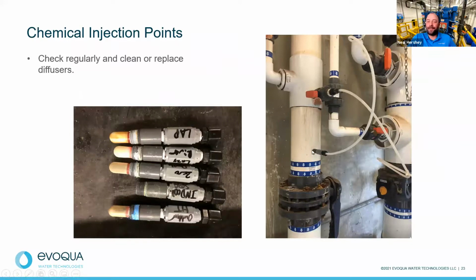In this case here, they're direct tapped into the piping, so to replace this injector you'd have to shut the system down and do that service, which could interrupt your schedule and your program and everything else. It's better to be proactive on these items and make sure you're planning ahead, building it into your routine plan, so it's not a surprise on a Friday before a big swim meet.